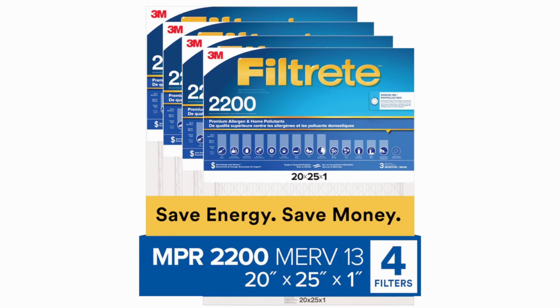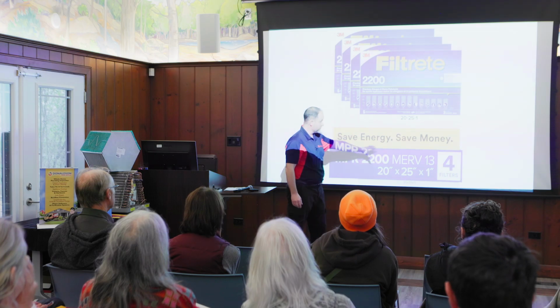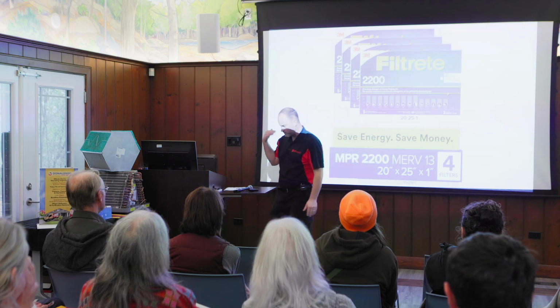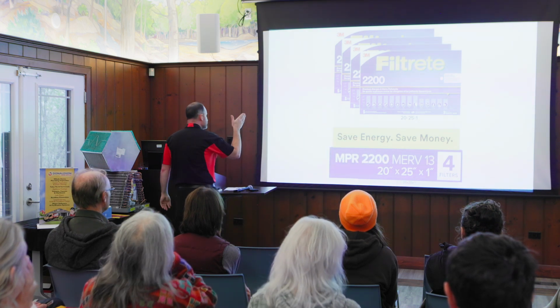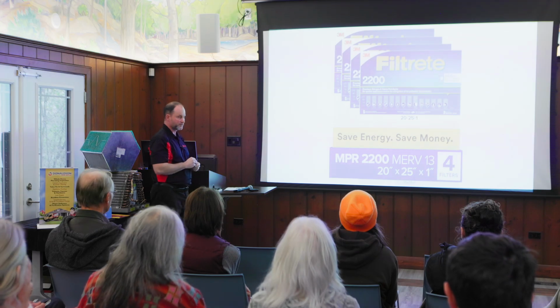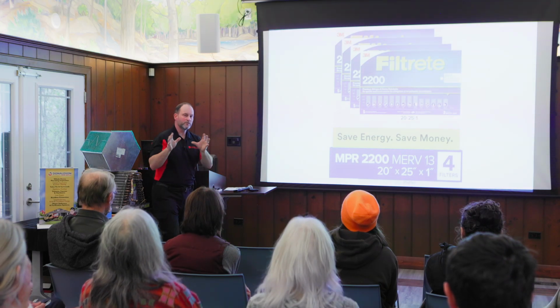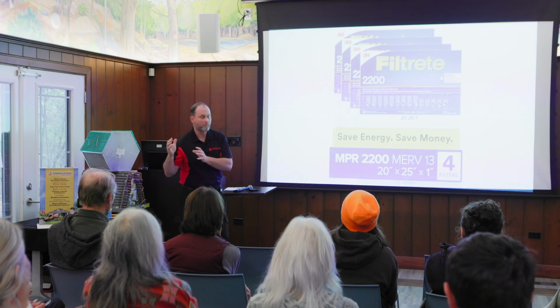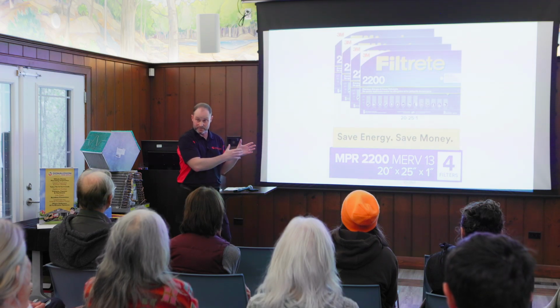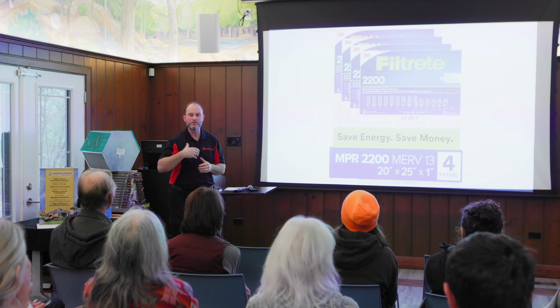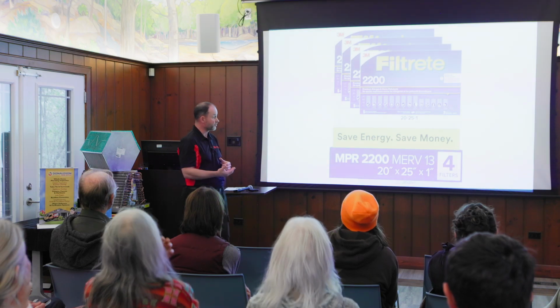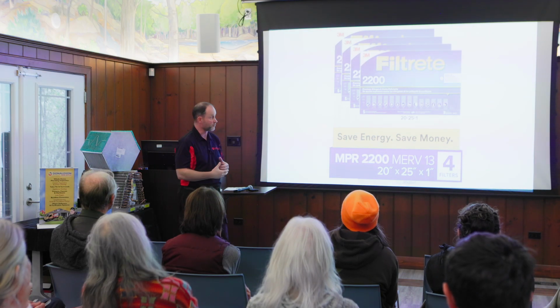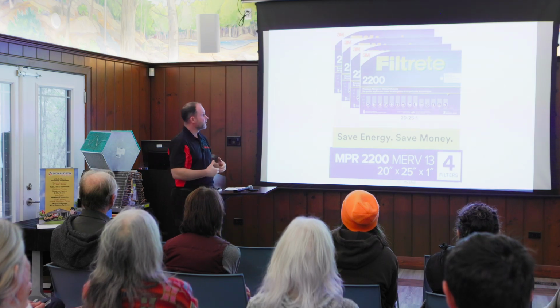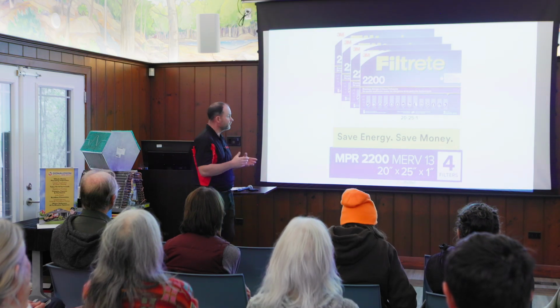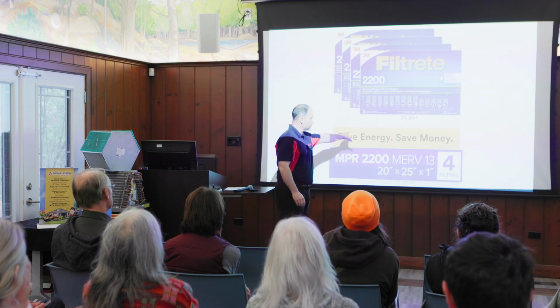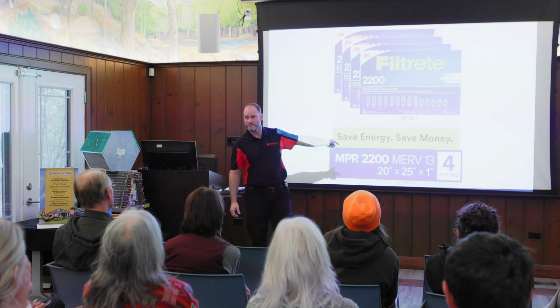This is a 1-inch filter from 3M. This is a MERV 13, and we'll talk about the different ratings in a moment. But that MERV 13 filter as a 1-inch filter, you as a homeowner need to understand that you have more than enough airflow getting to that system for the size of equipment that you have. Is your return air ductwork large enough? Do you have enough return air grills? Are all those return air grills pulling air from within the home? Do we have enough supply open? And if you know all of that, then yes, you can get away with a filter like this.